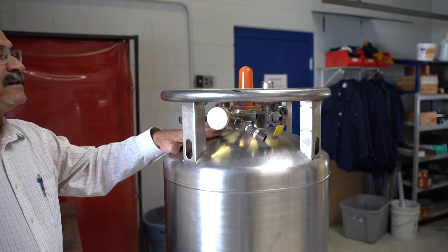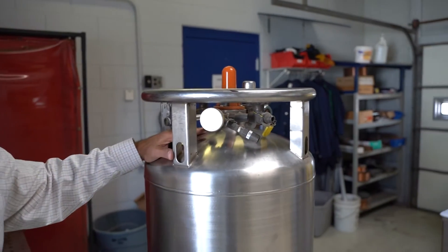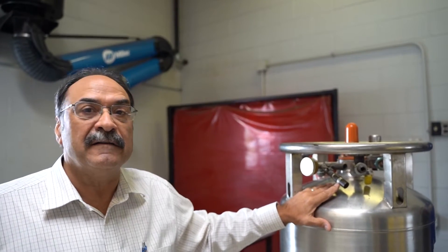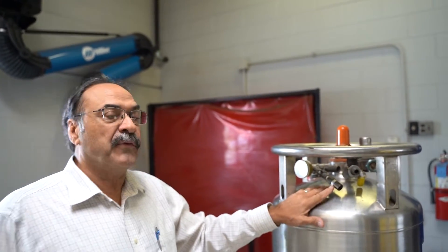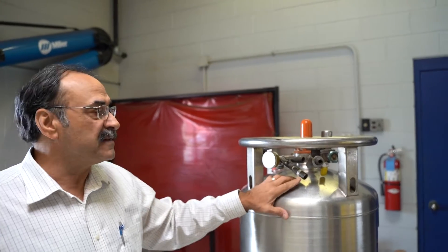There is what we call a burst disc on each tank, and the burst disc is the last fail safe. The burst disc does not reseat — it will just burst and let the gas out of the tank before any permanent damage can happen or the tank becomes dangerous. The pressure valves set on a liquid cylinder for gas usage are going to be about 350 PSI.